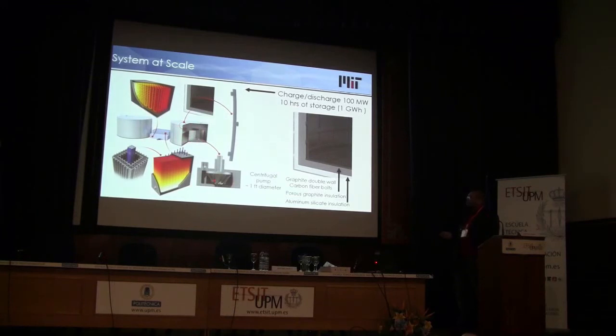The pumps are actually quite small, only about a foot in diameter, so a third of a meter or so. You don't need a tremendous flow rate—this is 100 megawatts, 10 hours of storage, so you don't need giant pumps. They're giant in the sense that the shaft is extremely long, because the pump sits at the very bottom of the tank so you can suck out the last bit of liquid, but otherwise their diameter is not huge.